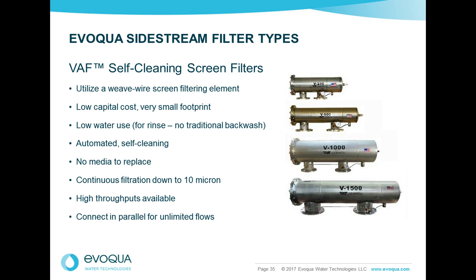They're a good choice for cooling systems, but you've got to note that if your particle size analysis shows that the bulk of your particulate is below 10 micron in size, these may not be your best choice because, again, they're not going to filter continuously below 10 micron. It's the smallest screen you can go with. So in those instances, go with something like a Vortisand.